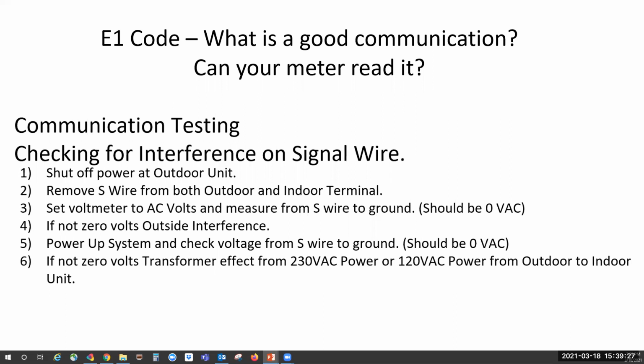To test this theory, you can run a temporary wire. Just make sure it's stranded wire. If you're just running temporary wire, it doesn't really matter if it's shielded, but you want to run a temporary wire between the S's. Usually 14 stranded wire is the best. If this solves your signal problem, then you know you need to run another shielded wire in between the units. If you have more than 24 volts on your signal wire, you'll have to run a separate wire, because this is what's giving us the E1 error code.